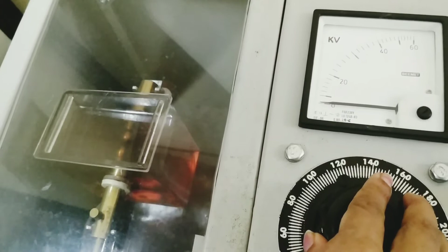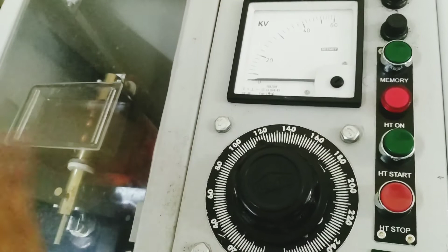You can see here the HT indicator, it is dark now, which means the dielectric strength has been lost and the electrode starts conducting. That means your oil has lost its dielectric strength.